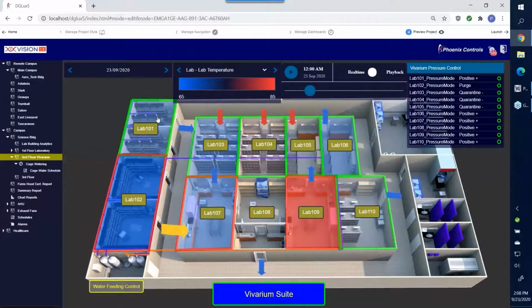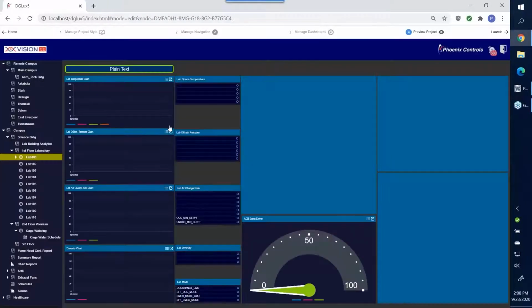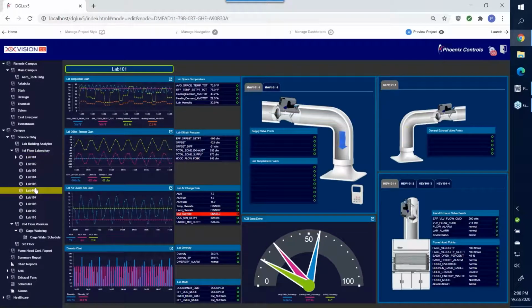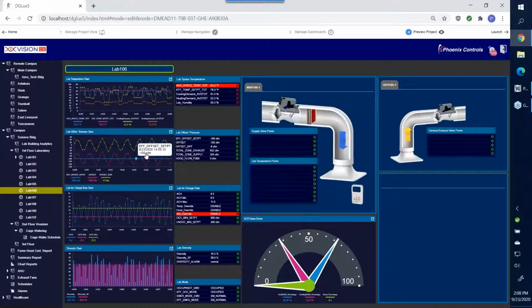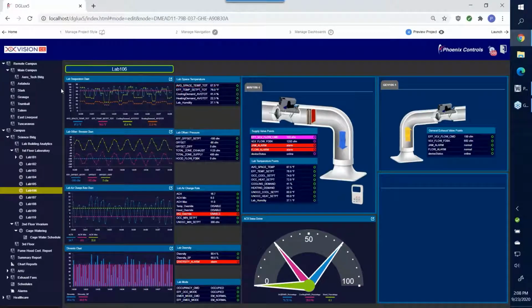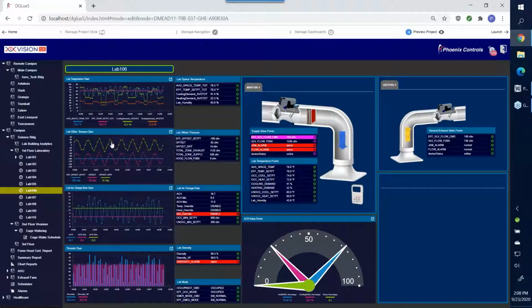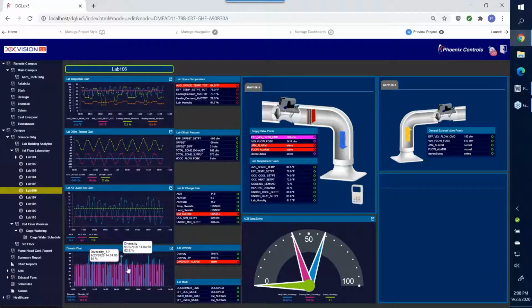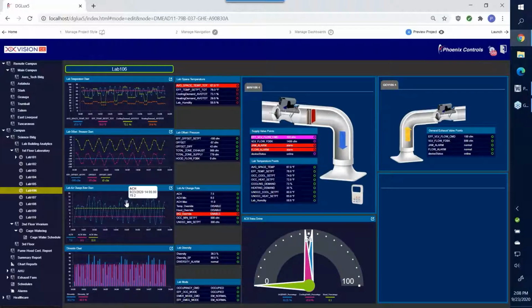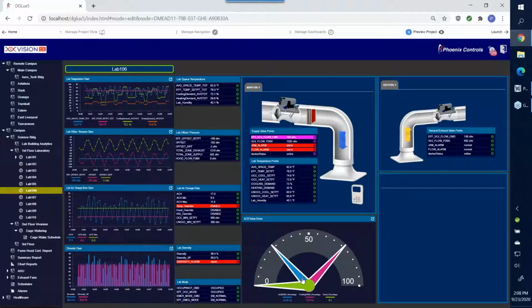Any of these spaces, you can jump into a particular detailed view of these spaces that you might find within a vivarium. In this case, you would have a full representation of temperature, your pressure points, your air change rate, and then your analysis in regards to labs with fume hoods. But you wouldn't typically have that in a vivarium. But it gives you history analysis of what's been happening, individual point analysis. And then you have the air change rate driver, which shows you what's driving an air change rate. So if your air change rate is running higher than you might expect or lower, you can look at this particular gauge and determine what's influencing and affecting that.